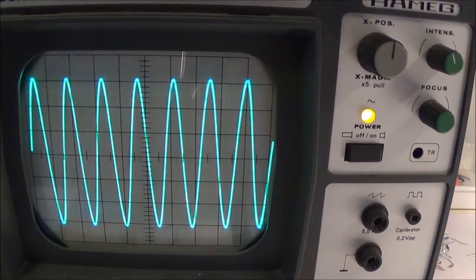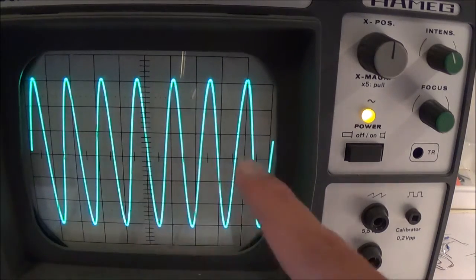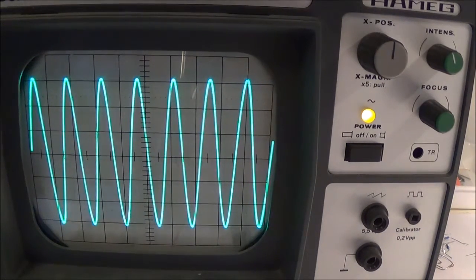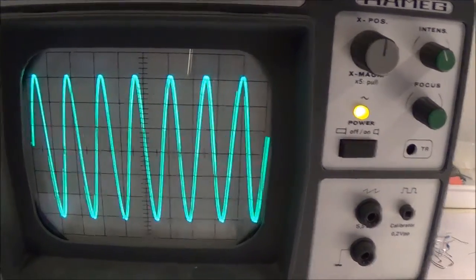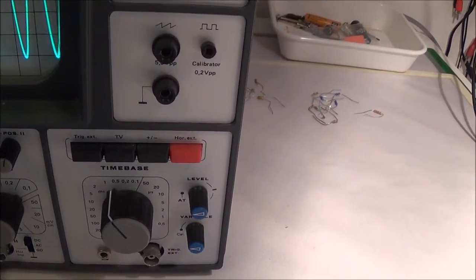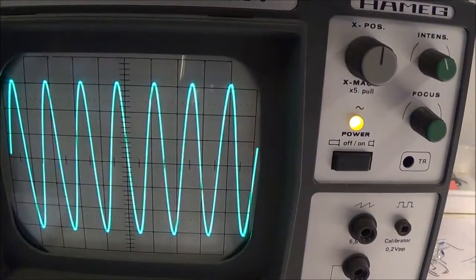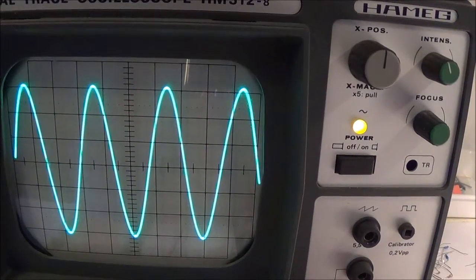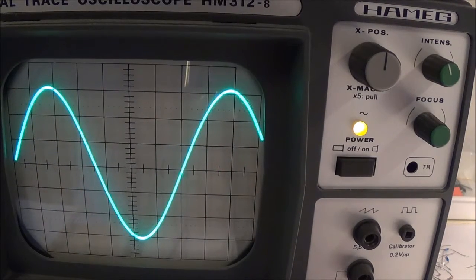Now, in order for me to measure frequency, like I said, I've got to get a clear, stable, readable display. Basically, you want to get it so one complete cycle of the waveform fills the screen. Evidently you can see here, this is all too scrunched up. So I'm going to adjust my horizontal time base. It's on 1 millisecond right now. I'm going to adjust that. That's still kind of scrunched up. I think that'll do it right there.